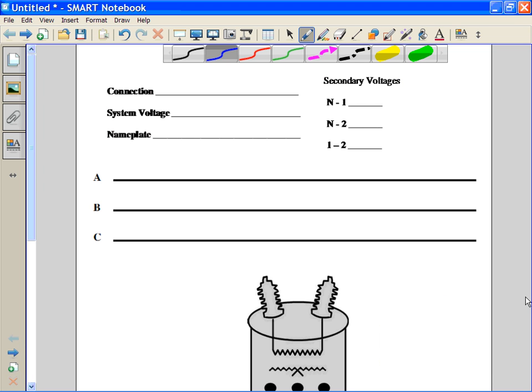This connection we're going to show here is probably the most common single phase connection that you will make in your career as a line technician. And it will be a single phase 120 volt slash 240 volt 3-wire connection.